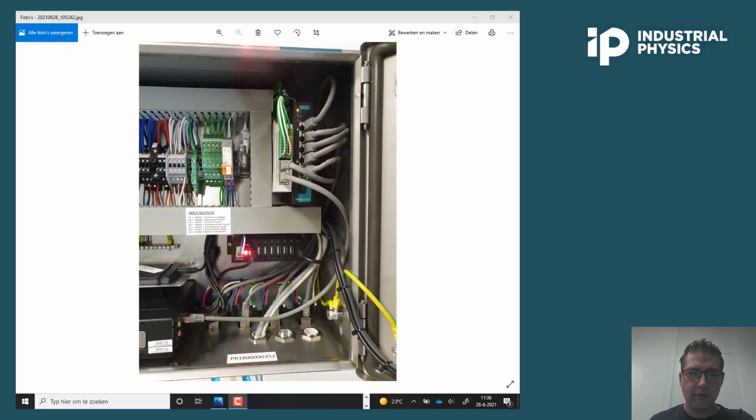Over here there's a picture from inside the control unit, and over here this is where the Baumer is located. So the Baumer is connected with an Ethernet cable that you can see over here that's running into the PC, and from that point there is another Ethernet cable going to the switch on the side, and all the 4 different cameras for the CU6 Control Unit are connected through the switch, through the Baumer into the PC. So right now it's correctly connected. So if this looks different, so if one of the cables is missing, this should be fixed.